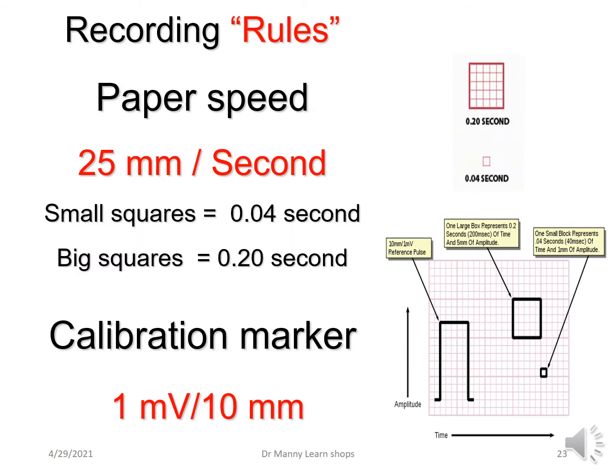As indicated previously in the paediatric course, there are recording rules. Paper speed must be set on your machine at 25 millimetres per second. At that setting, every small square equals 0.04 of a second or 40 milliseconds, and every big square equals 0.2 of a second or 200 milliseconds. The calibration marker must be set at 1 millivolt, which is the same as 10 millimetres — otherwise, what you record will be incorrect.